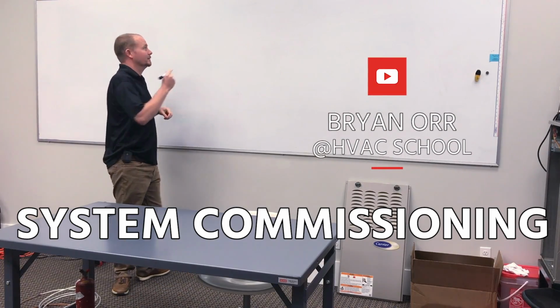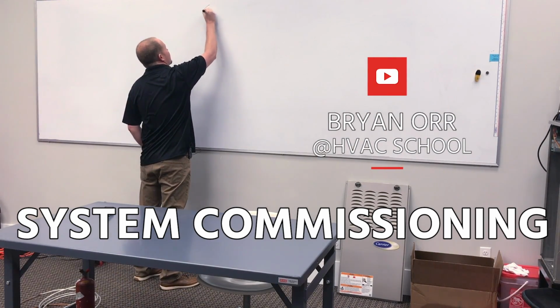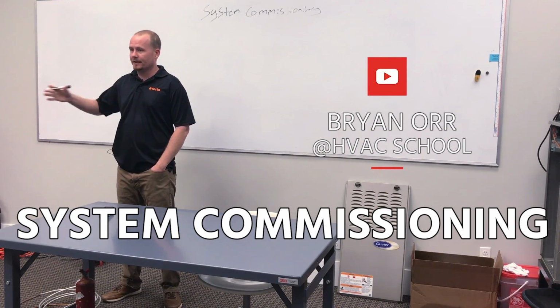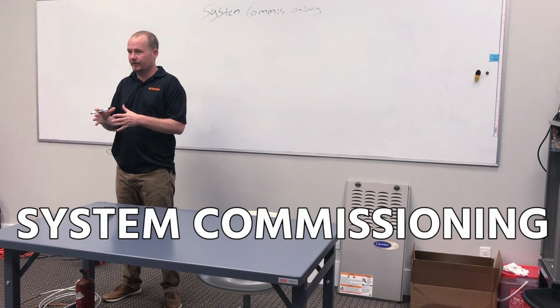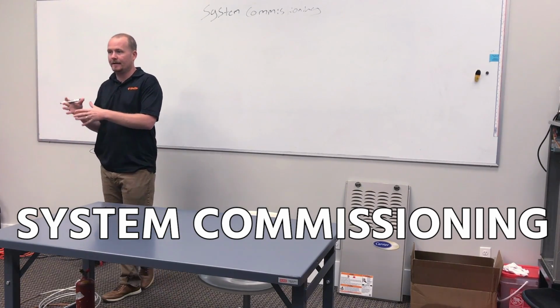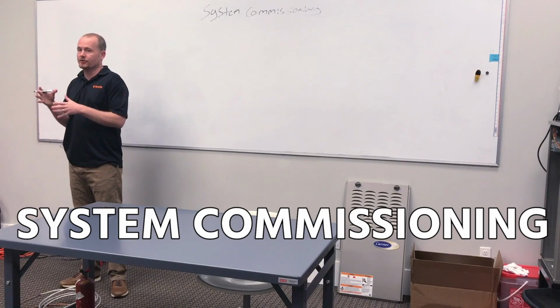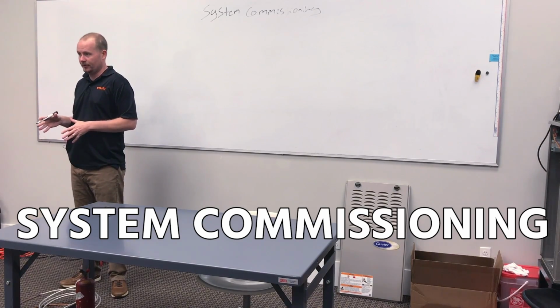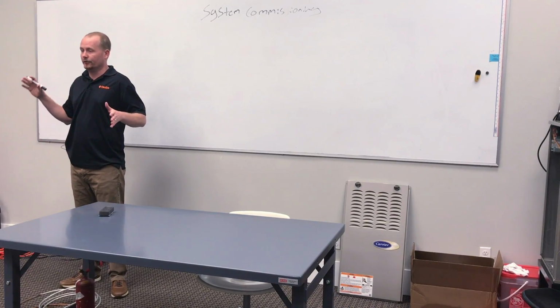We're going to talk a little bit about system commissioning, so I'm going to make it quick and we're just going to run through it, because sometimes we talk about these in fragmented ways and then you don't put it all together. But every time you're doing a new system setup or you're doing a major component replacement, you have to do a full system commissioning. So let's say you replace an evaporator coil, you replace a compressor.